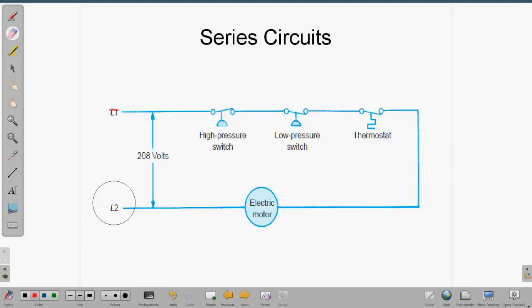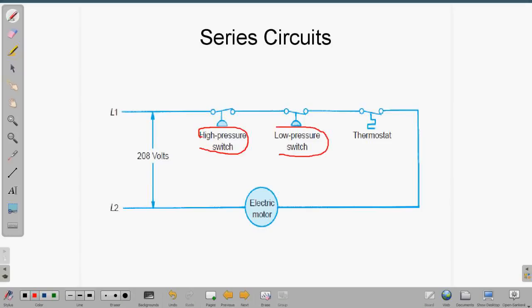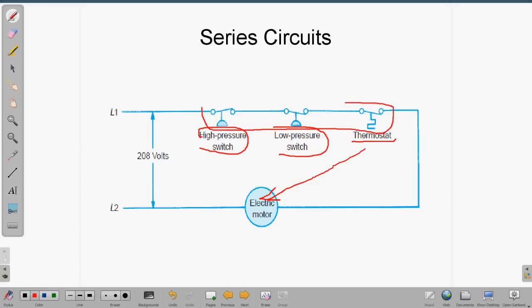A series circuit in HVAC is usually a control circuit. If the high pressure switch opens up, you lose power to the compressor, which will save that electric motor. If the low pressure switch opens up, it also breaks the circuit to the motor. If the thermostat is inside the motor and the motor overheats, that also breaks the circuit. Usually your protection and control devices are in series — if any one of those three opens, it's going to kill the power.